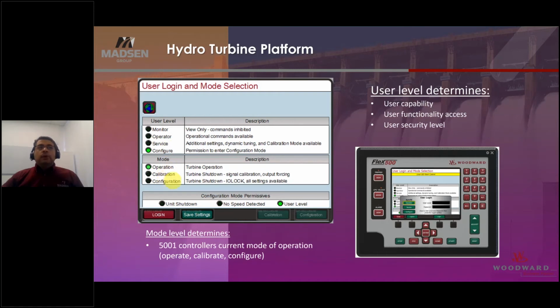You can do some calibration. So if you're looking at actuating the valve while the turbine is off, or you would like to start and open your gates, we have the capability to do in-house calibration using the unit itself. All you have to do is have the user level that allows you to do that, either the service or configure user, and then you take the unit out from operation to calibration mode.